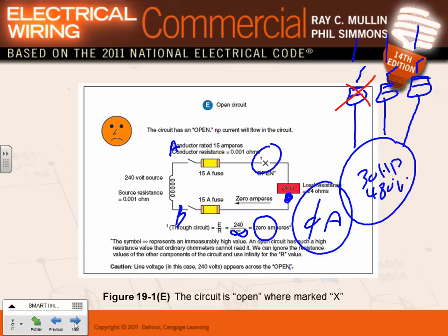With a three-phase load, the current on each one of these will go 173 percent, I think, of normal. So you have 73% more current on each phase. Now, if this fuse was 100 amp, and now I'm pulling 173 amps out of it, what condition do you have? Overload. The fuse will trip.